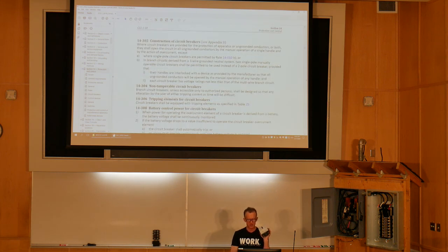Construction of circuit breakers. Where circuit breakers are provided for the protection of apparatus or ungrounded conductors or both, they shall open the circuit in all ungrounded conductors by manual operation of a single handle. There's the single handle opening all 3 phases. All right? So that takes care of construction of circuit breakers, and we'll see you in the next one.